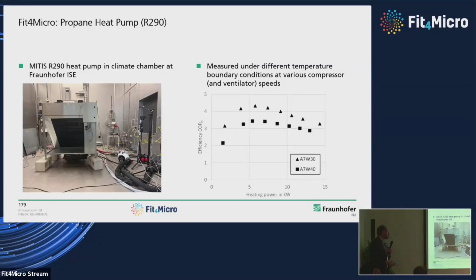We looked at lower temperature conditions here, which A7W40 means air 7, water 40. And you see some efficiencies here, the thermal COP for these, which again reflects mainly the point that if you have to provide 30 degrees, efficiency will be higher than if you have to provide 40 degrees.